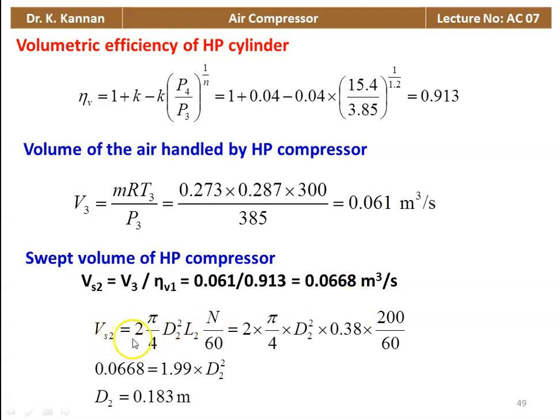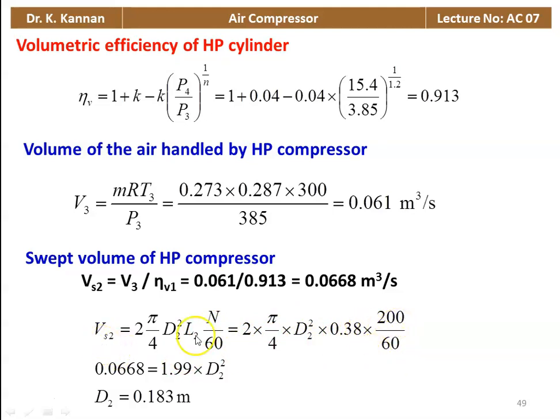Swept volume of HP compressor: Vs2 = V3 / η_V = 0.061 / 0.913 = 0.0668 m³/s. Also Vs2 = 2 × (π/4) × D2² × L × N/60. Substituting: 0.0668 = 2 × (π/4) × D2² × 0.38 × 200/60 = 1.99 D2². So D2 = 0.183 meter. Diameter of the HP cylinder is 0.183 meter.